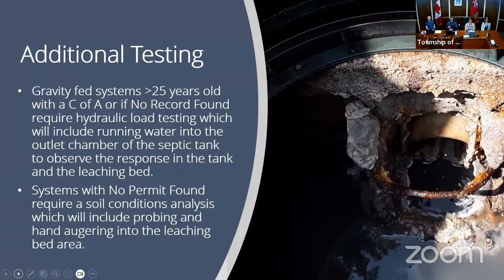And then if it did rise, is it able to drop back down in, let's say, an acceptable amount of time? So if it is able to eventually drain, that's maybe a sign that your system isn't at its peak operation. However, it is still able to accommodate that morning rush type flow. So that may be a conversation with the homeowner to say, maybe be cognizant about the amount of people that are at the property and how much flow is being used at any given time. Try to spread that out and maybe start preparing for a future replacement of this system.